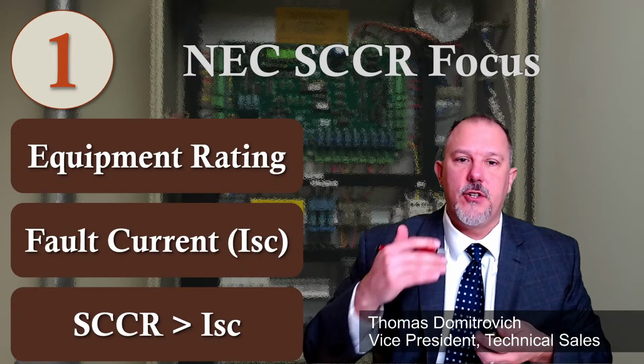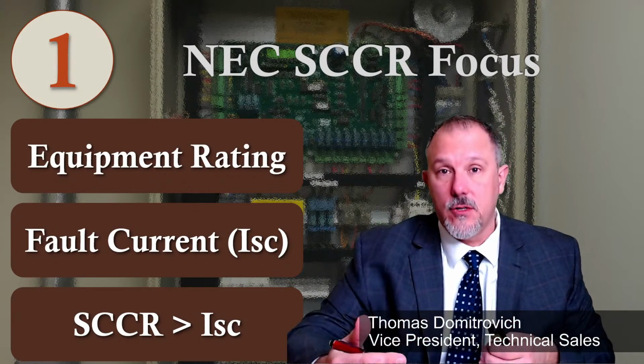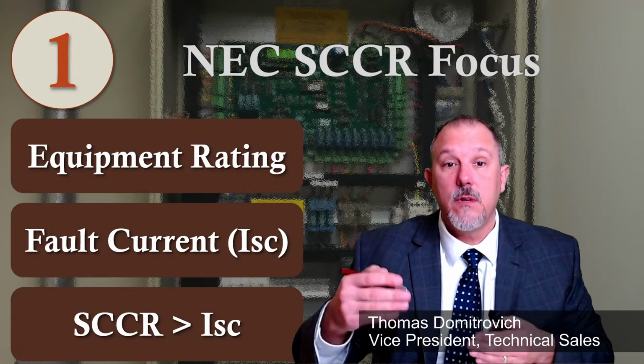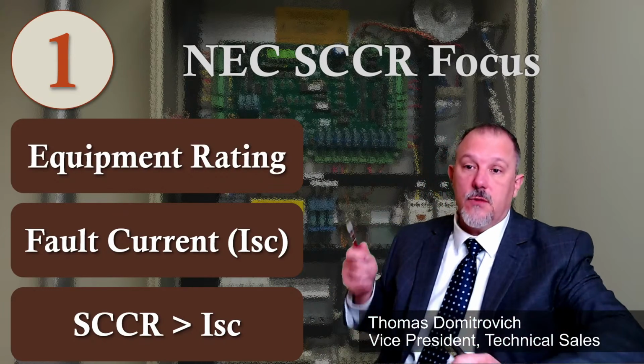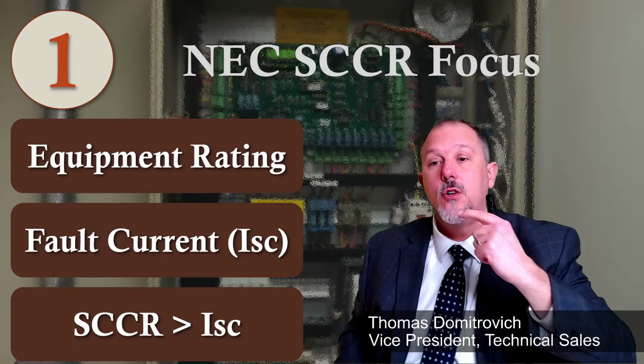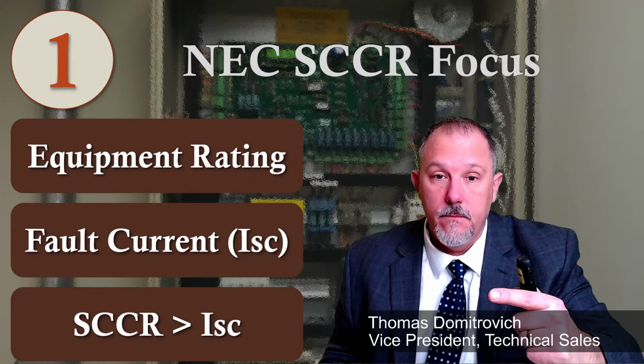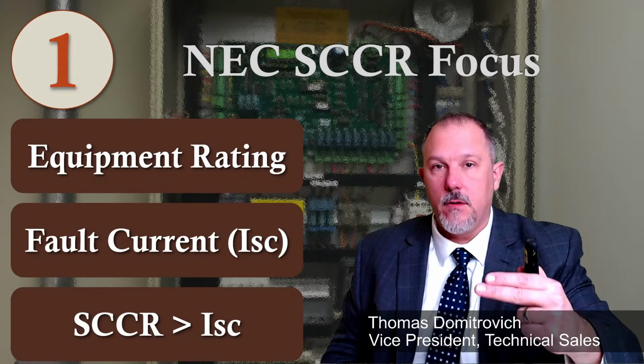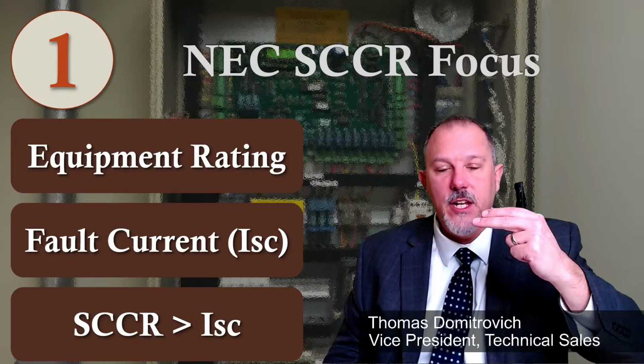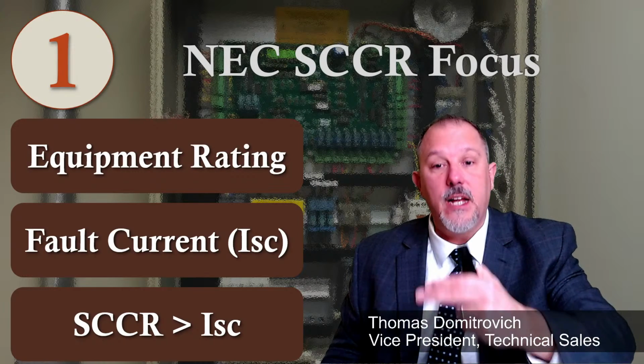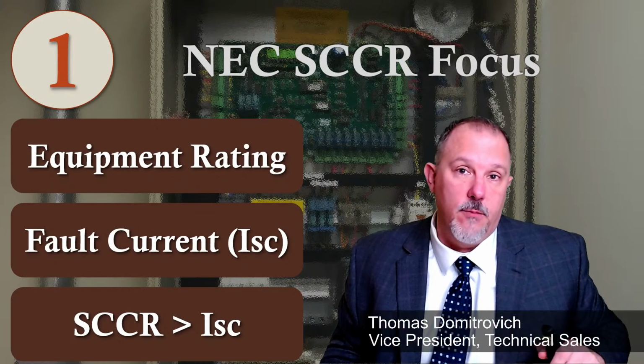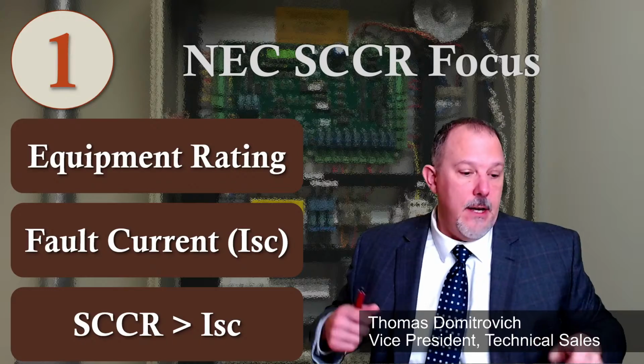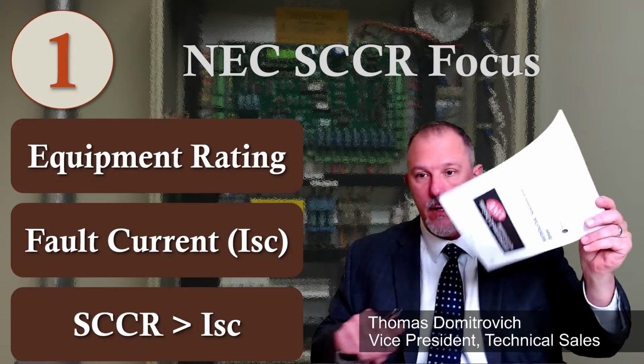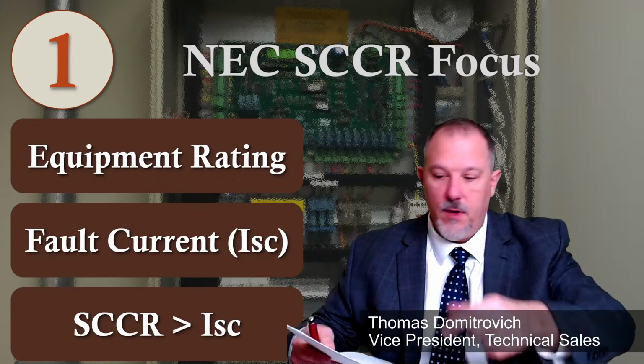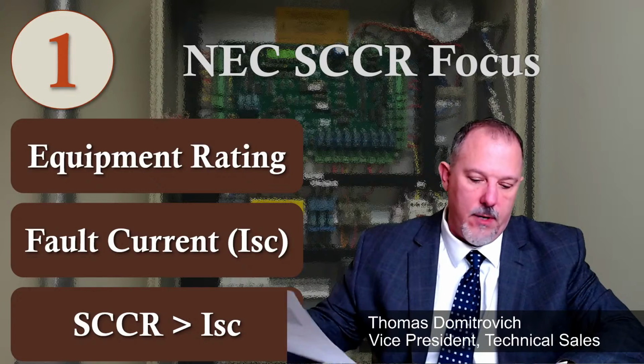So what's important to understand is that the National Electrical Code made some recent requirements to spell this recipe out. You need to know what the equipment is rated for. You need to know what your available fault currents are. And then you need to make sure that the short circuit current rating of your equipment is greater than the available fault current.